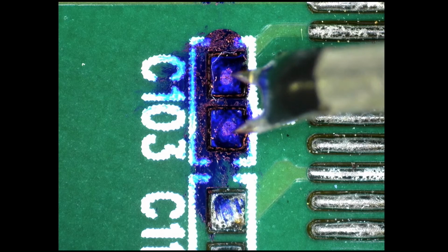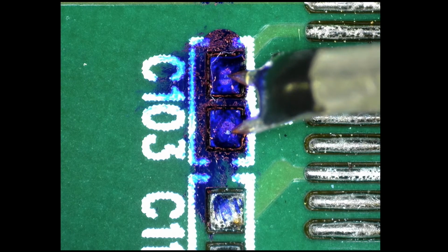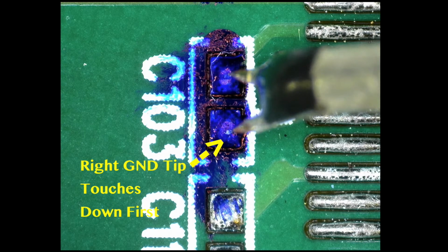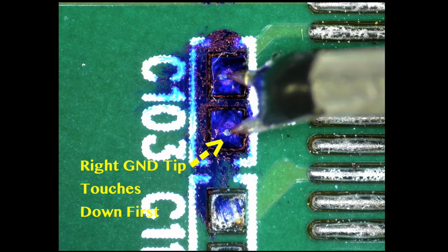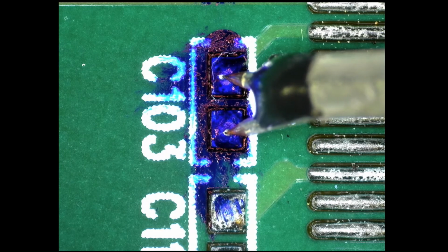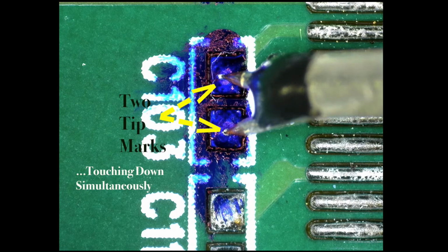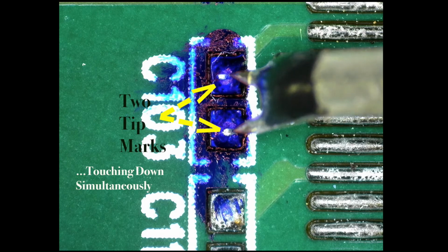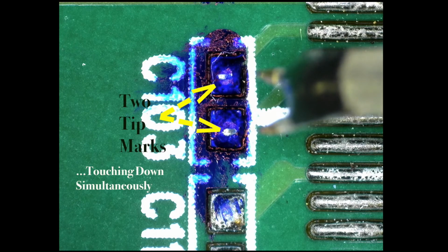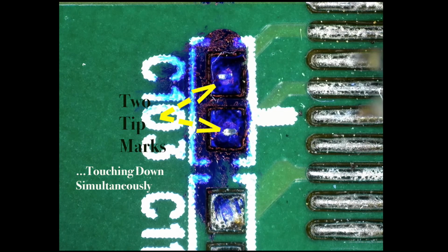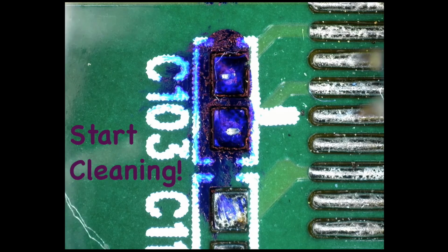Keep in mind that if you only see one tip mark, this means that only one probe tip is touching down. Therefore, planarization adjustment is needed. In this case, the right ground tip touches down first. The two probe tips are properly leveled when you see two tip marks on the solder bumps when lowering the probe with a TP60 or TP300 probe positioner. After you confirm that both tips have made contact using the probe skid marks, clean up the solder bumps with industrial alcohol after probing.